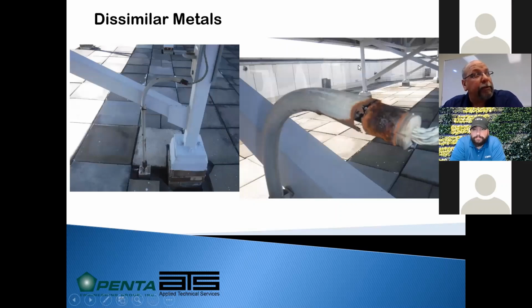This was a fully copper system that was installed on structural steel, and then the copper was routed into a galvanized steel conduit. This is the down conductor. Copper cable would actually extend all the way to the ground. But this is really good evidence of galvanic corrosion and what happens with prolonged moisture exposure between dissimilar metals.